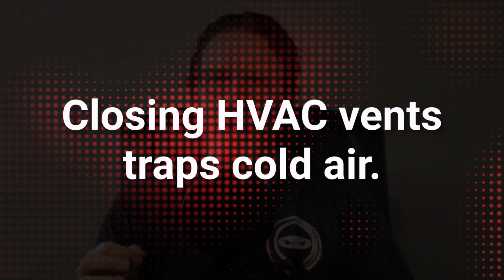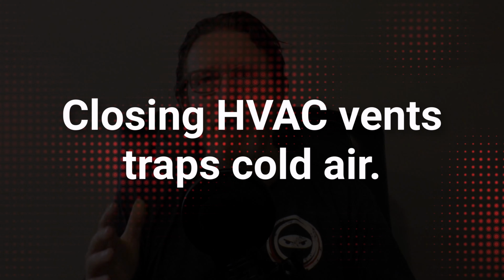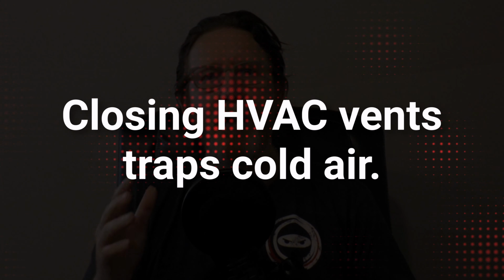Now here's a myth I want to bust right now. A lot of people think, I'll just close the vents in the rooms that I'm not using and that'll push the cold air upstairs. But here's the problem with that. Closing vents doesn't redirect air, it traps it. Your AC system has what's called a static pressure. Think of it like blood pressure for your ductwork. When you start closing vents, that pressure builds up, the system works harder, the compressors start failing, motors start seizing, and your upstairs still doesn't cool down. You've just created an expensive problem on top of the original.